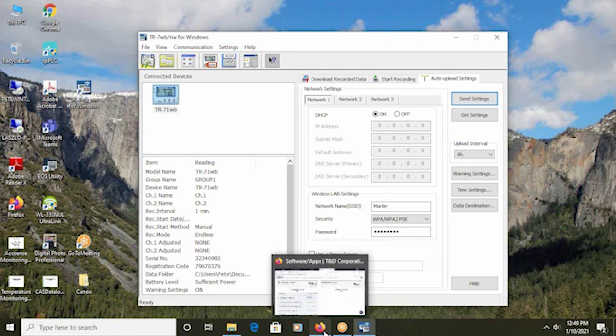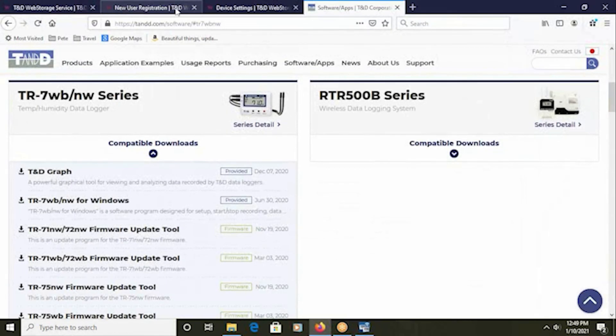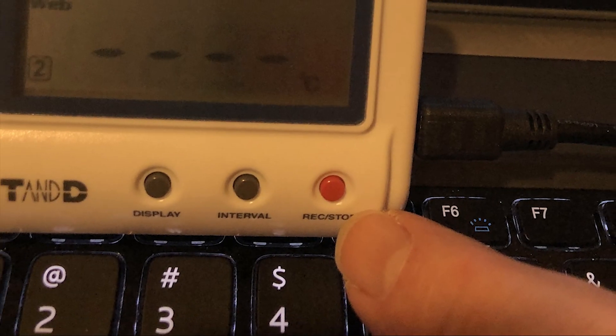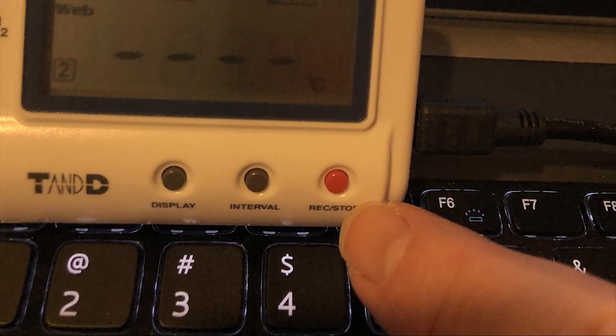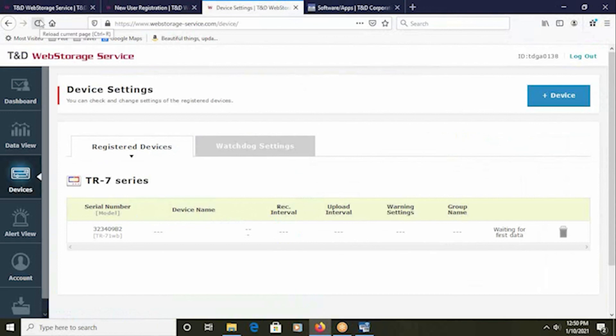Once you've got the access configured, you can return back to the web storage service. And as a quick test, by very quickly pushing the record stop red button on the face of the logger one time with a quick push and release, that will force the logger to initiate a communication immediately without waiting for the upload interval to elapse. Once that is complete and you've forced that upload, within about five minutes, you will see the settings transmitted to the web storage service, which tells you that your configuration is complete.